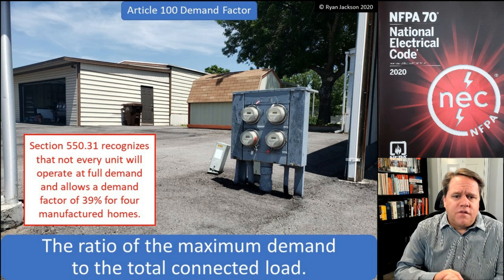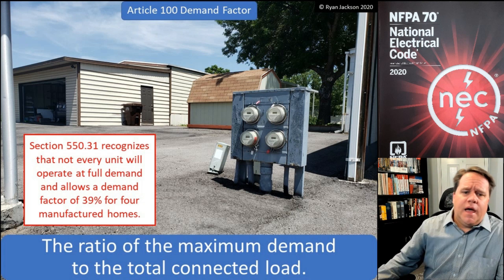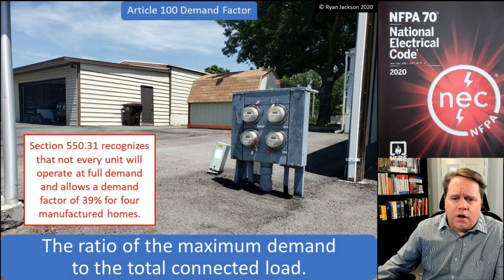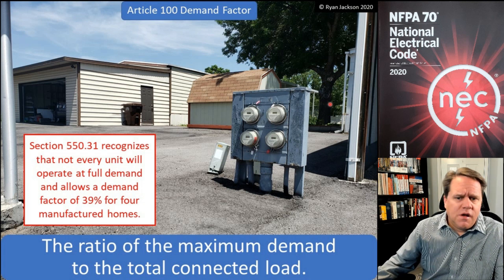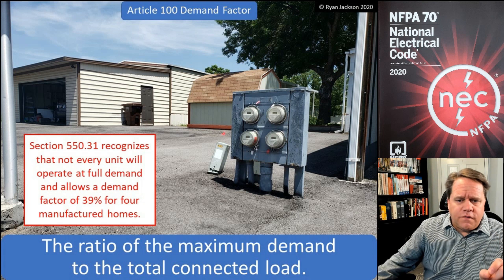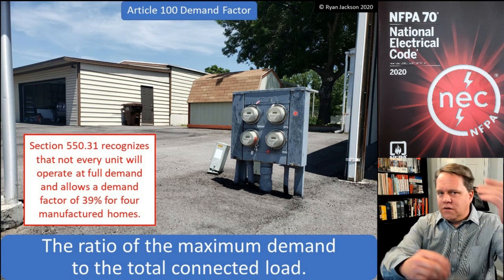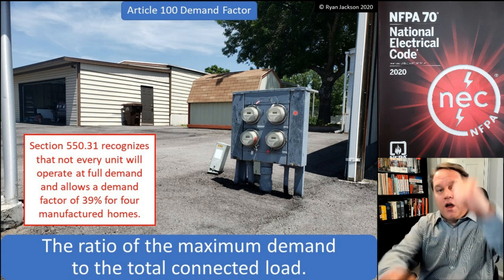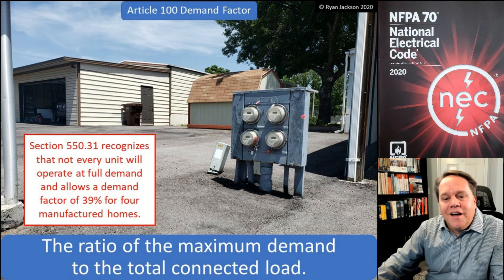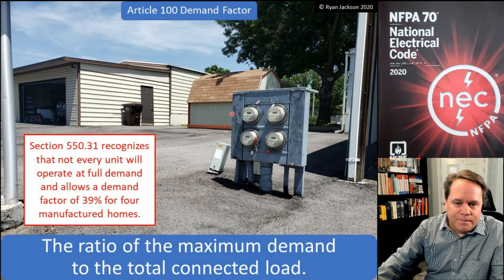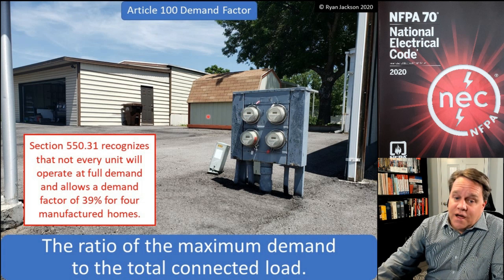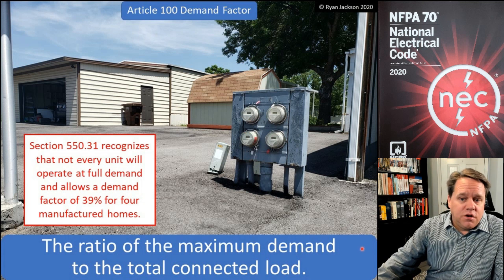Here in the picture we have some manufactured homes and a service that supplies them. Each one of these has — I'm guessing — a 100-amp breaker. I took the picture but didn't get into the service disconnect, so each one of these has a 100-amp breaker. From the 100-amp breaker to the unit, we have to size that basically at 100 amps.